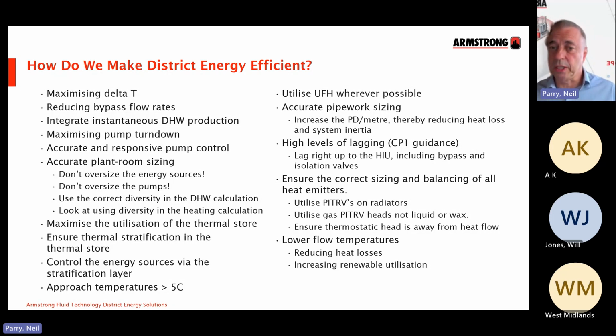Absolutely use the correct diversity in the hot water calculation. Look at using diversity in the heating calculation, something that's recommended in CP1 again. Definitely maximize the utilization of that thermal store, and ensure that you don't connect it in such a way that allows flow through the vessel, so you have circulation around the sources and through the vessel, because that will minimize the amount of energy that you have in the store and raise that return temperature back to your sources. So you need to ensure the stratification there in that store.